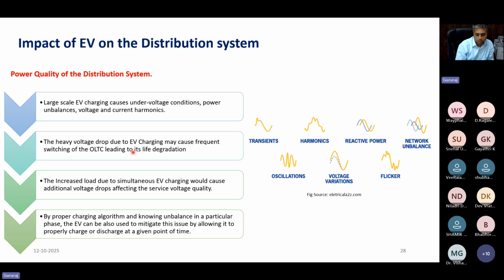But today in this country, we do possess only mechanical on-load tap changing transformers, which have limited operations, up to 10 to 12 operations probably per year. So if you have these EV charging stations connected to these feeders where this OLTC is connected at the substations, naturally frequent tap changing is expected, because as a basic concern, the OLTC is designed to maintain nominal voltage of 1 per unit at the bus where it is connected. So most of the buses are still a radial network. So naturally there is frequent OLTC tap changing, and that will degrade the life of the OLTC as well.